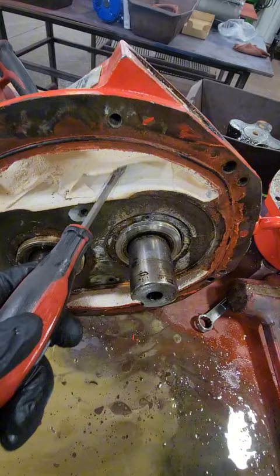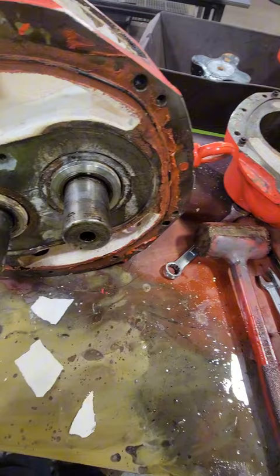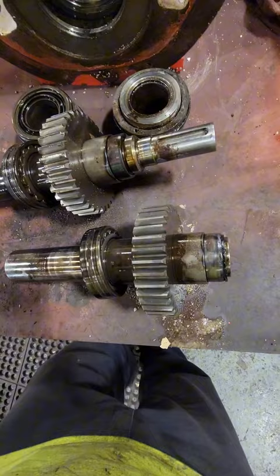We have two small shims that are located right behind those rotary lobes, and if I scrape a little bit right inside of here you can see something that really resembles baked lays — I'm going to try these out later around lunchtime. Now we'll need to get a breakdown of the pump; we will go through this thing, check every part and piece, replace all the seals, bearings, and o-rings, then put it back together and make this thing run again like it's brand new.